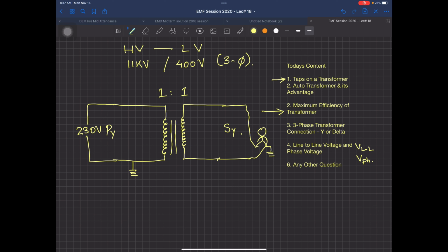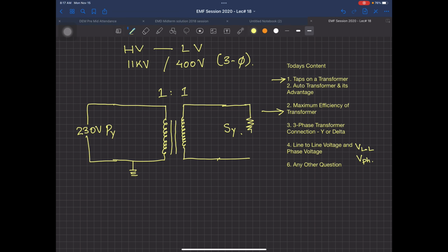Now the problem that arises when the taps are used is this: if it's a 1:1 ratio transformer, you are going to attach a load over here. This load is going to be a variable load, and I'm showing it by a resistor and a variable inductor. Certainly if the load changes, then the amount of current flowing, which is your secondary current, is going to increase.